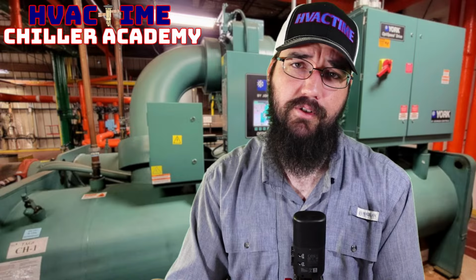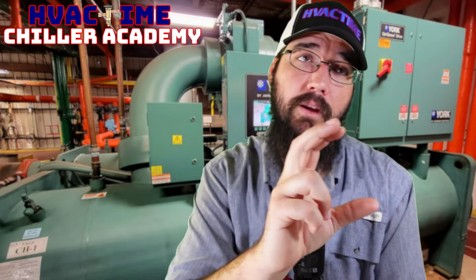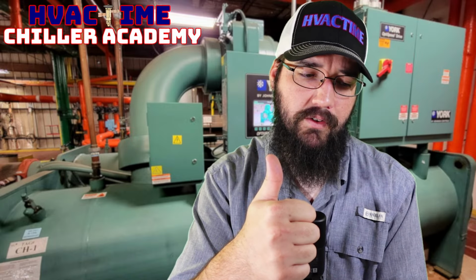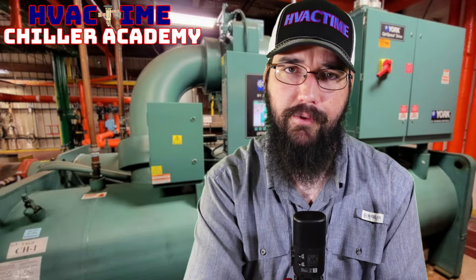But there's a couple of big key unlocks for you that I think have really helped me, and that's drawing conclusions between what I learned in light commercial to heavy commercial and chillers. One of those key breakaways is we're processing water instead of air, right? RTU or a walk-in cooler, we're processing air over the coil. Chiller, we're processing water. That's step number 1. Everything else stays the same. Heat transfer aspects are the same. All of that's the same.